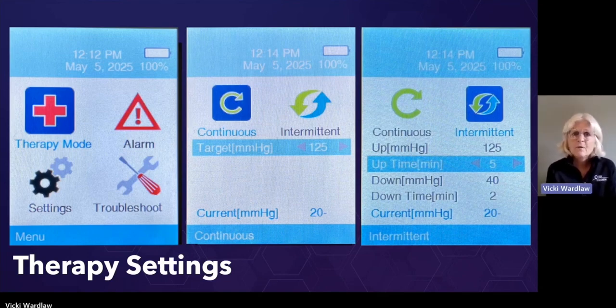If you didn't want to save your changes, you would highlight no, and it would just divert back to the prior settings. If you wanted to go into an intermittent mode, you would change from the continuous to intermittent by using your right arrow. Now intermittent is highlighted, and those are the values you would need to have in your prescription in order to run a variable intermittent. So you would need an up amount of pressure, and you would need an amount of time that you would like the device to stay at that pressure. You would need a down pressure value and the amount of time there as well. Once you highlight, make your setting, highlight, make your setting, and then exit, you will have to accept those changes again by pressing the center button. And then the device will run that sequence for your patient until you change it.